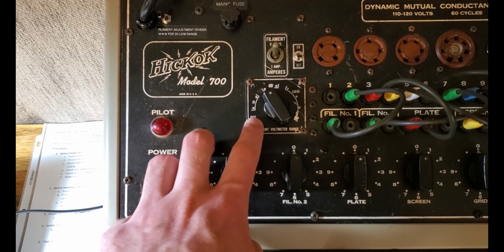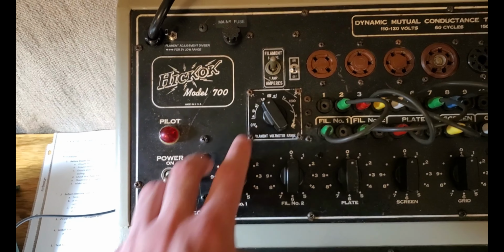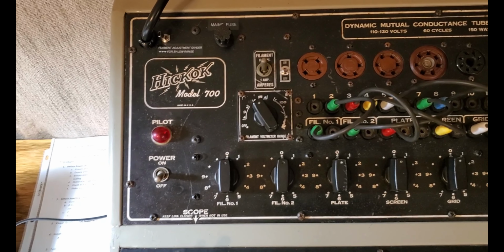These two toggle switches replace the function of the broken wafer, and one of them is a simple on-off for the filament. So as you rotated this switch from the off position to one of the voltage ranges, it automatically turned on the filament.